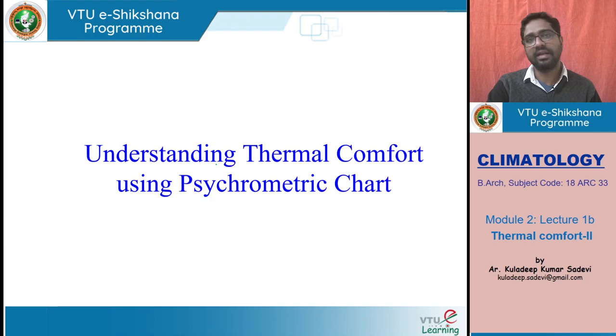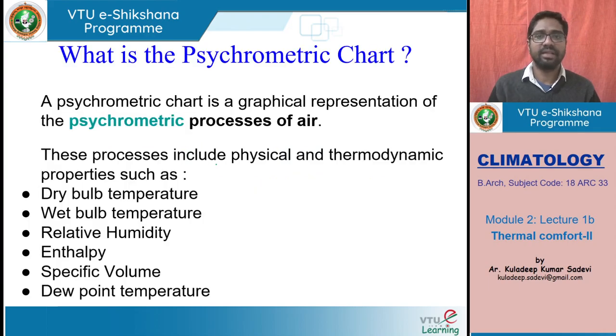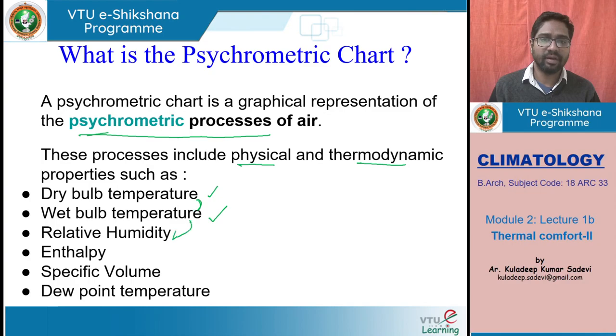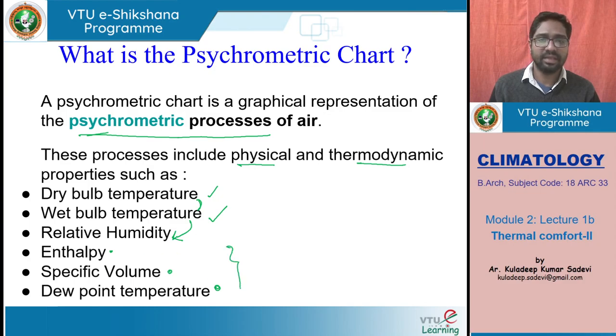We will now see what is psychrometric chart and how it can be used to analyze climatic parameters of different places. Psychrometric chart — the word means physical and thermodynamic properties of air — and we are trying to chart out all these parameters, all the psychrometric processes of air, into one single chart. The parameters are: dry bulb temperature, wet bulb temperature — if we know these two, relative humidity is factored into the picture — and enthalpy which is nothing but heat, specific volume, and dew point temperature. These are the six parameters represented in a psychrometric chart. This is a rough picture of a psychrometric chart — we will discuss in detail how it is used and what inferences can be drawn.